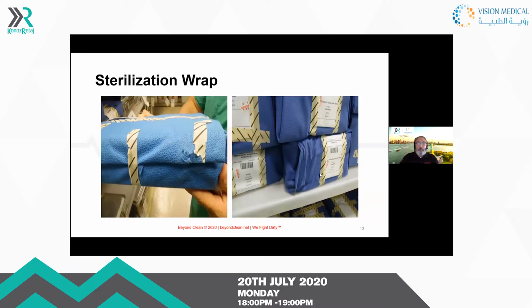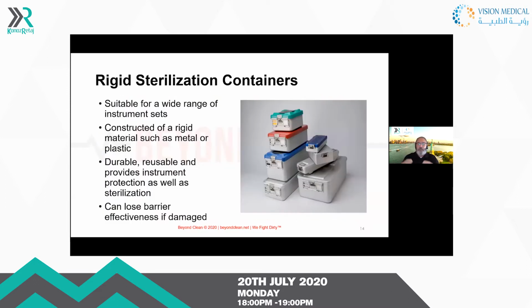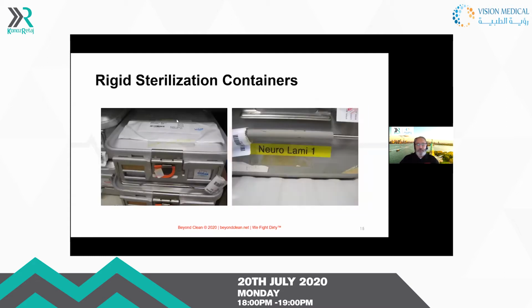So now we think about rigid container sterilization systems. We know that they're suitable for a wide range of instrument sets. They're typically constructed of rigid metal material, usually aluminum. They're durable and they're reusable. They protect your instrumentation, and one very important part, that last bullet point, is that they have to be maintained. You have got to make sure that you're taking care of these sets, these containers, to ensure that they do not lose their barrier effectiveness, which they can do if you're not inspecting them properly.